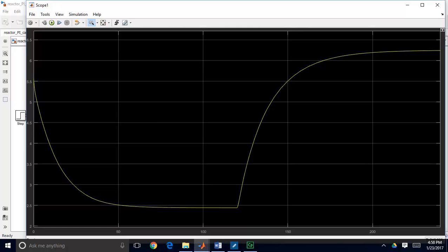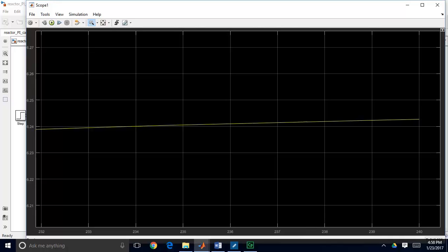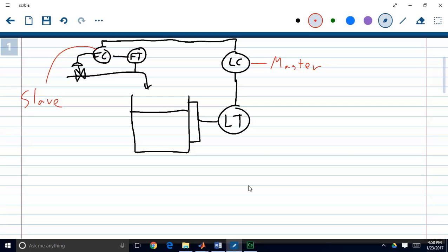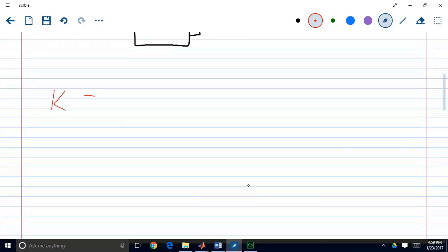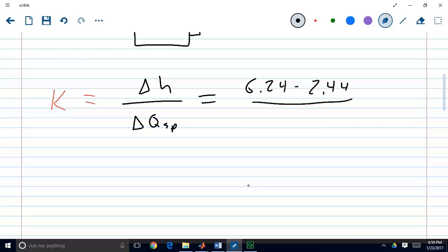First I want to get the process gain, finding the final and initial values going from one steady state to another. My final steady state value is about 6.24 and my initial steady state value is about 2.44. So the process gain K is equal to the change in tank height divided by the change in flow set point: (6.24 minus 2.44) divided by (8 minus 5), which equals approximately 1.27.